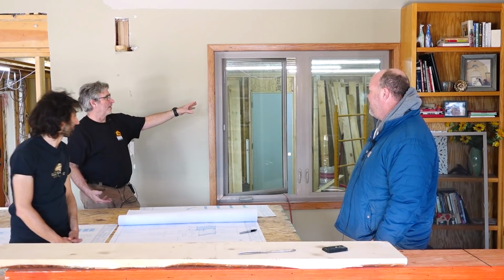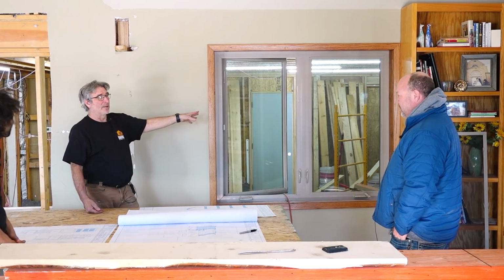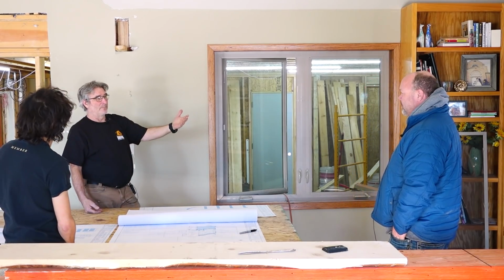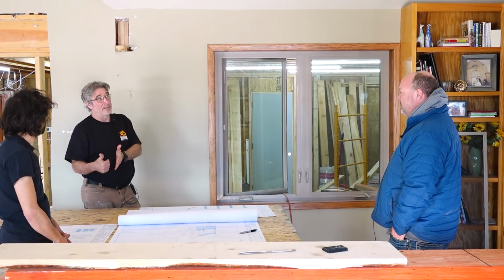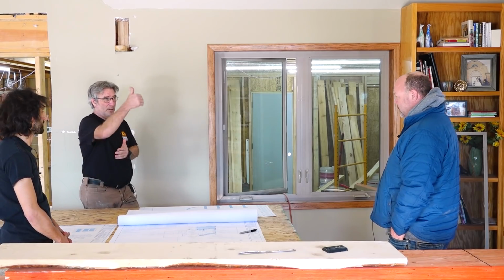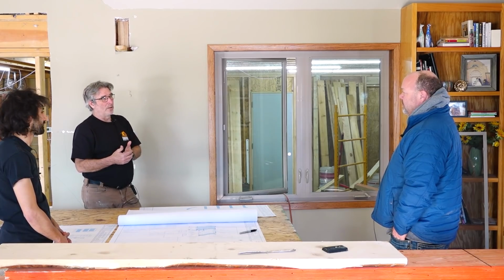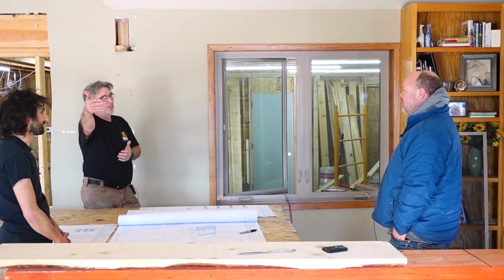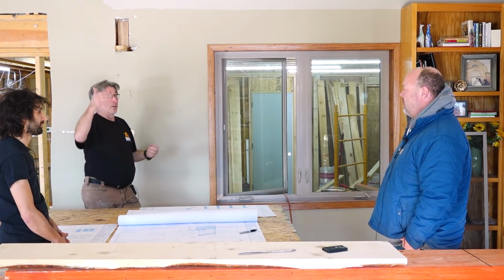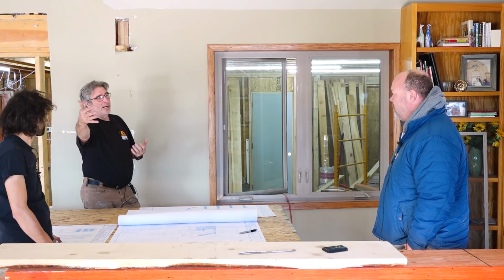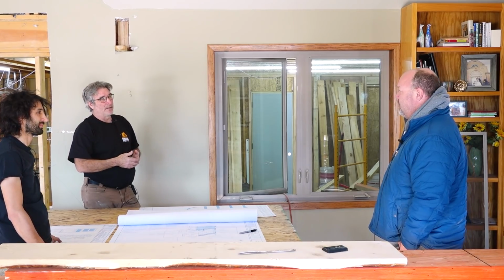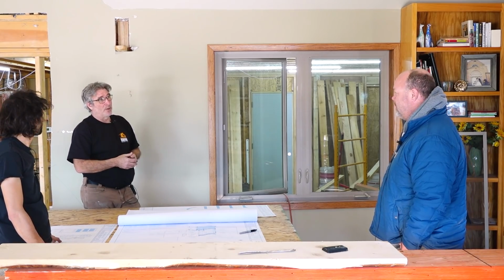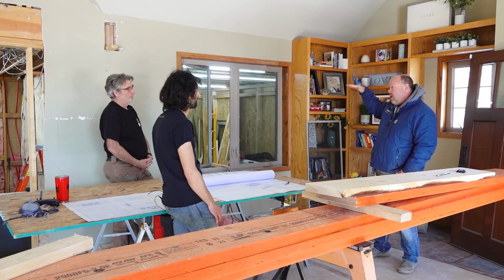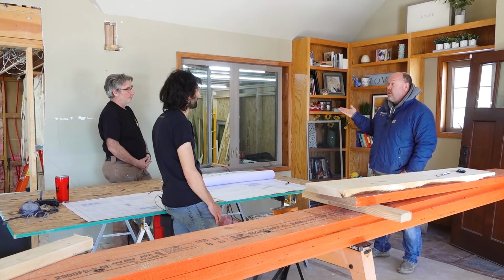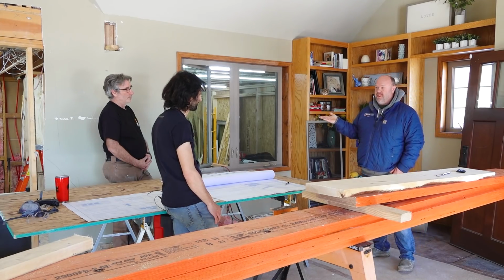So like the sunroom now, we've got a lot of glass going into it, so we'll probably have a higher AC requirement than a standard stud wall. And if it was south facing it'd be different than east facing - south with glass is going to require more AC. Correct, probably more heating too. Your eaves coming out on your fascia and soffit - the further you extend those, it changes the angle of the sun, which will actually help with the load.